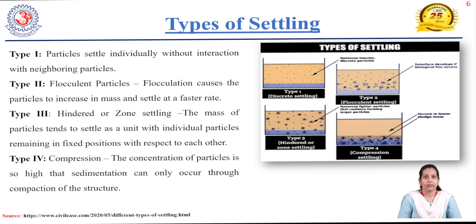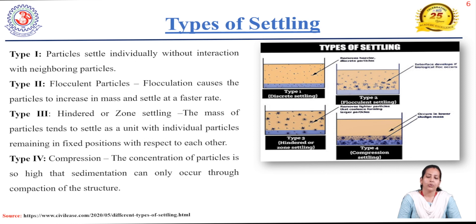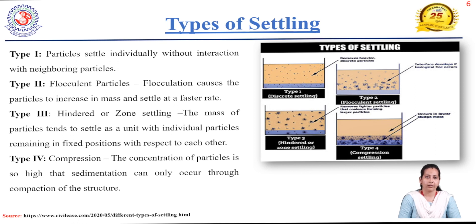There are four types of settling. Type one: particles settle individually without interaction of neighboring particles — a natural gravity process with no chemicals. Type two: flocculent settling, where flocculation causes particles to increase in mass and settle at a faster rate. After adding specific chemicals, the suspended or colloidal particles form a floc and tend to settle at the bottom of the tank.